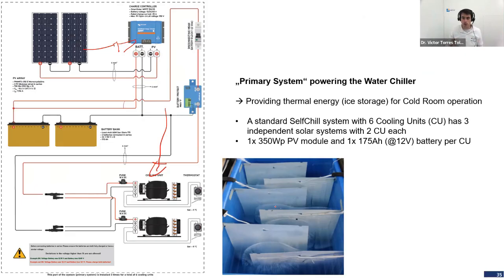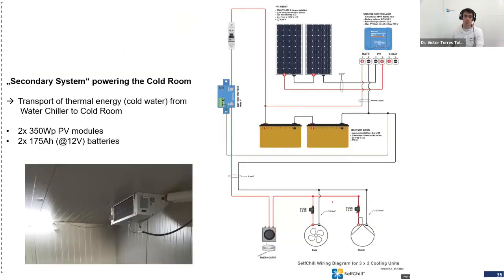And then the cold water, so we saw here, this is ice, ice, ice, like around every evaporator plate, we have ice. Perhaps you cannot recognize it in the picture. And the rest is water. Yeah. So water, ice, ice, ice. You have here some water. And then from the bottom of the water chiller, you get cold water that you pump inside the cold room. So this is the working principle.